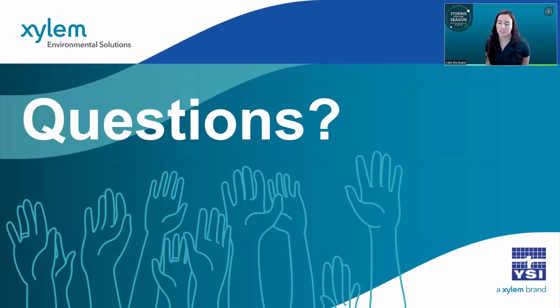Yeah, I'll hop in. Jess, feel free to pop in if I miss anything. Generally, you don't want to ever be storing your sensors submerged in water. For short-term storage, we have a humid air environment. That's because, particularly for those more finicky sensors like pH, ORP, and ISEs, it can deplete the reference solution over time. The sample water, the water it's sitting in, will basically pull the chemicals that are in the sensor out of it. And that's going to deplete the life of your sensor.